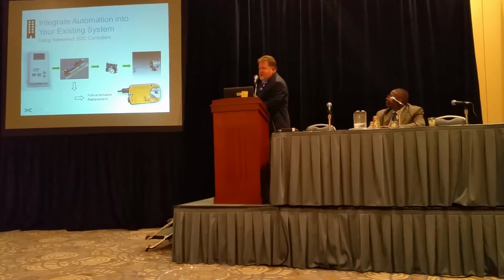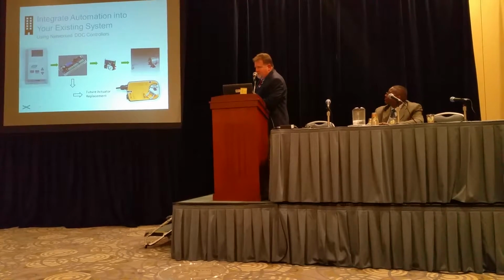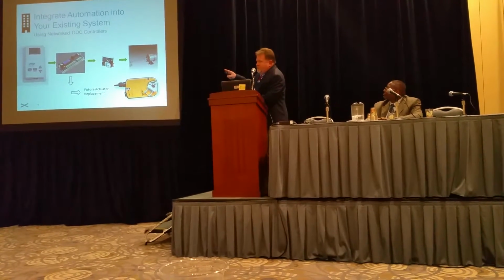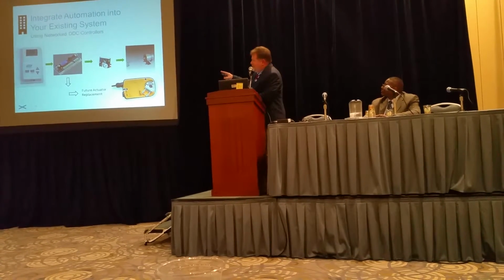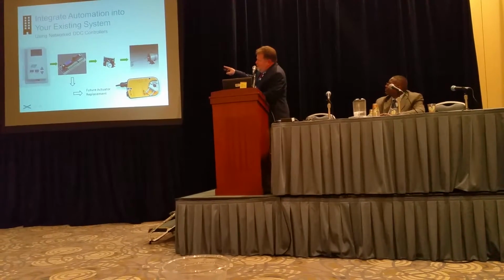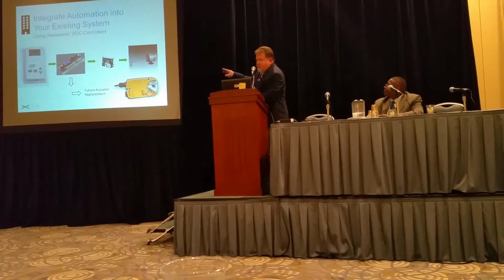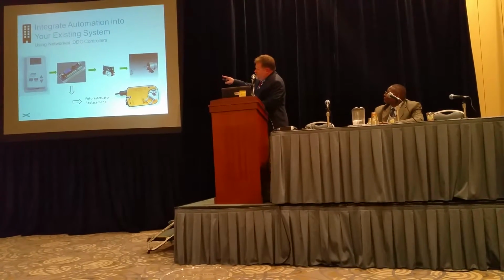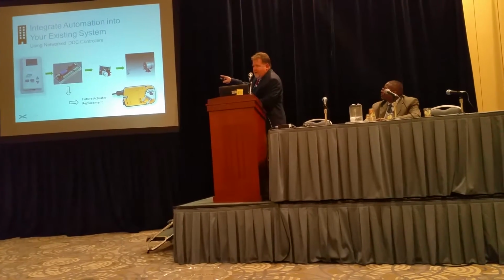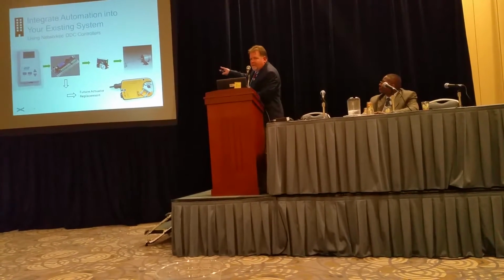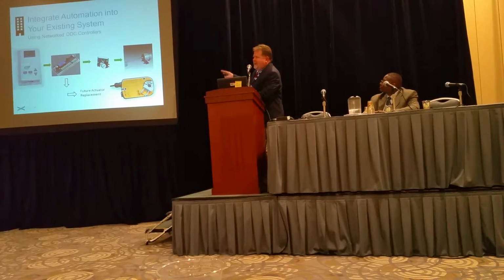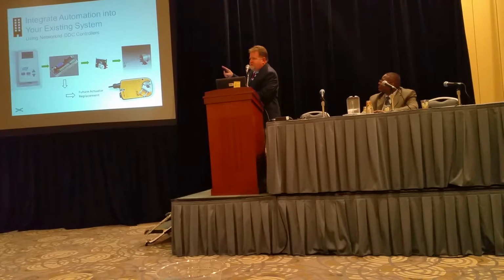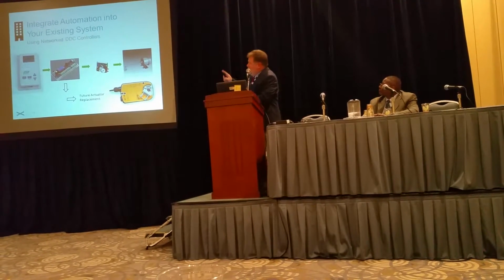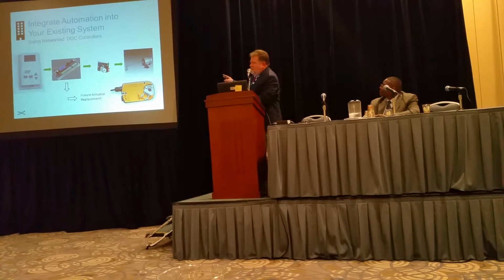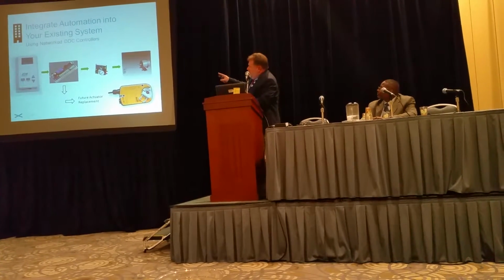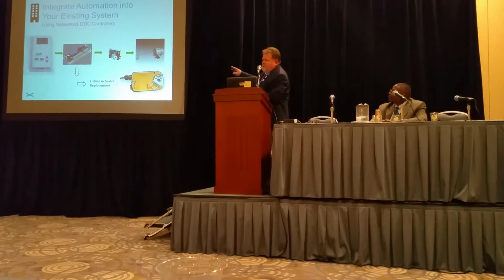This is the new system. This is how you integrate into the existing control system that you have. We have a new digital thermostat, a state-of-the-art digital sensor, which to the right communicates with a digital controller, and then that controller tells the transducer how much air to send to that old diaphragm to open and close the valve. So simply what we've done is we've taken pneumatic control, which has no intelligence whatsoever, and we're controlling the end unit, the actuator, by allowing a certain amount of air through the pressure transducer to open and close that damper.